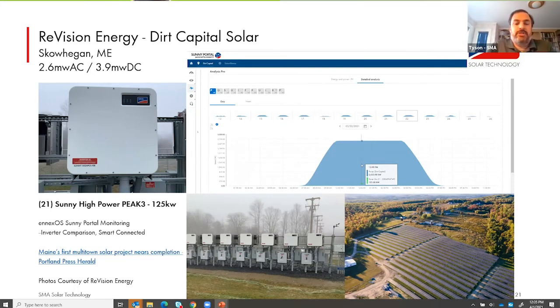This brings me to the production curve you can see at the top of the slide. Dirt Capital is a 3.9 megawatt DC and 2.6 megawatt AC power plant, which translates to 150% DC to AC design ratio. At this high design ratio, which you might also know as an inverter load ratio, or ILR, you can see here that the PV system is able to achieve maximum output relatively early in the morning around 9:30 a.m., and then it stays there until relatively late in the day, about 3:30 p.m. This is about 6 hours of maximum output, which is fantastic.